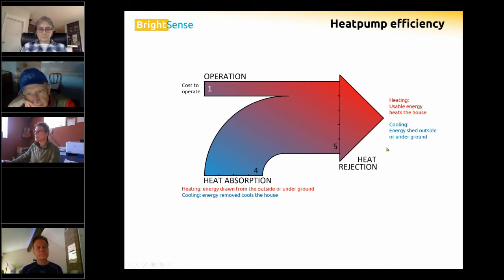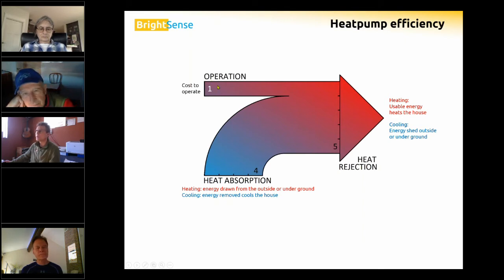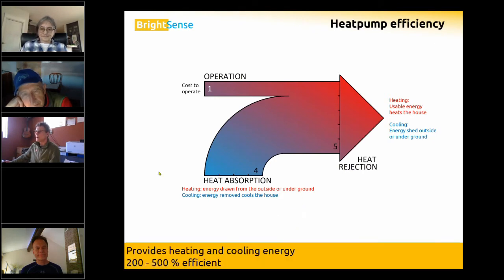In heating mode, we get five usable units. In cooling mode, if we turn it around, the cooling effect would be four units. We'd need one unit to operate, and we'd shed those five units of thermal energy outside. This illustrates how a heat pump works and how our efficiency comes about.